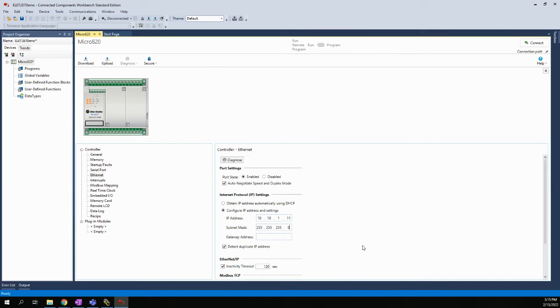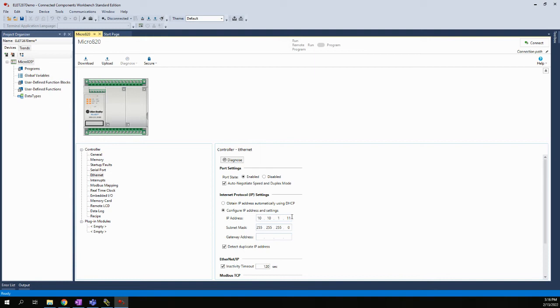So the reason why that's important is because when I get connected and when I download, it's going to take that Ethernet setting and it's going to set that into the controller. And if you had a different number there or if you put obtain automatically, it's going to put that setting in the controller. And if you change something and you didn't realize what you changed it to, you might have a very hard time getting back connected to this controller again. So this is a very important step. At this point, just for what I'm trying to show here, I just want to show the main step of how we're going to get connected.